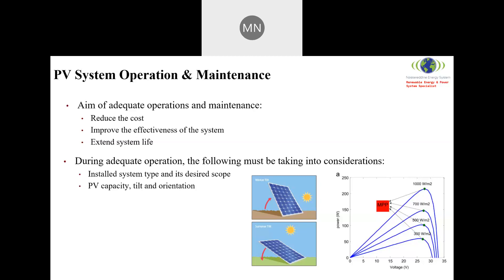When it comes to operations, you need to understand your PV system's capacity, tilt, and orientation. For example, if you're installing 100 kilowatt PV panels but they are not all oriented and tilted at the same location, you cannot assume you have 100 kilowatt or 80 kilowatt peak. If you have a tilt east and tilt west, the peak of the two arrays will never occur at the same time, so it's very important to take this into consideration.